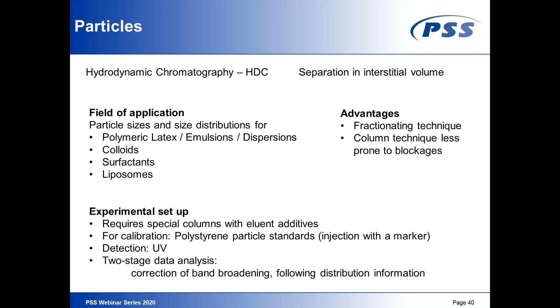How does it look, and what do I mean by that? Well, first of all, let us look at how an overlay of the different calibration standards with the markers would look. You see here on the right-hand side the marker. It looks like one peak, but it's the marker for all of the peaks, so we get a very reproducible elution here. And then we see our standards eluting with decreasing radii. We start with 1000 going down to 46 nanometers here.